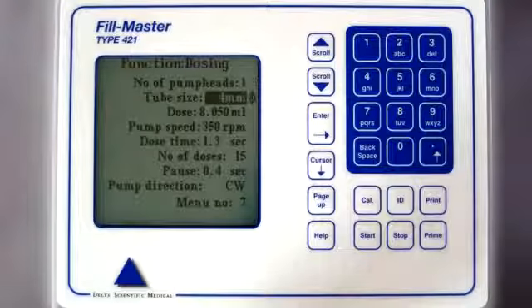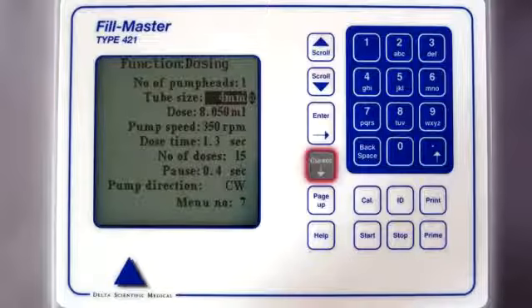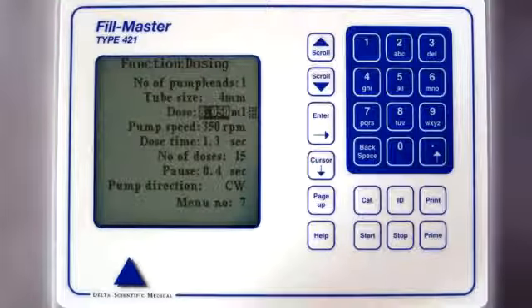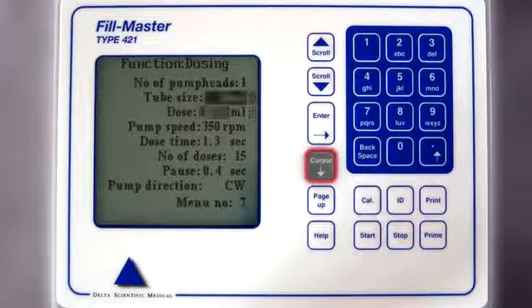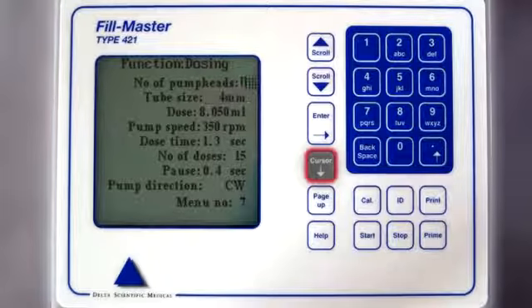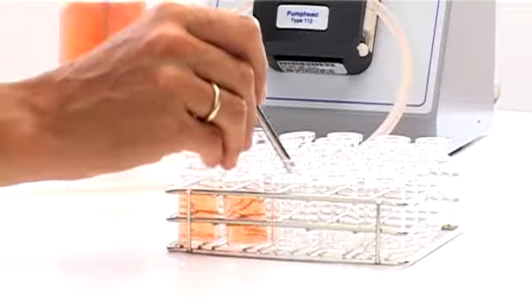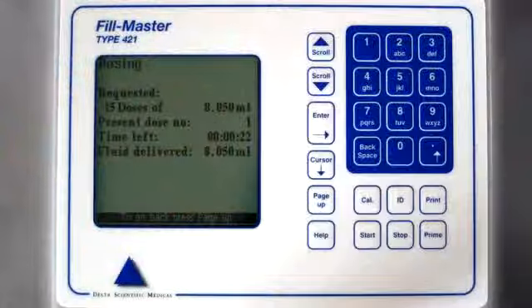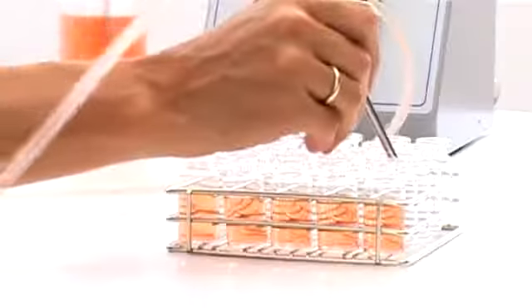In all windows, you can use the cursor button to move the cursor to the next field where something can be inserted or changed. Pressing the cursor button briefly will make the cursor move forward, but if you press the cursor button for more than a half second, the cursor will move backwards as long as you keep the button depressed. You have now completed a setup for dispensing rapidly and accurately. Press Start to begin the sequence. A new window tells you how far into your process you are now. To go back and change something in the setup window, just press Page Up.